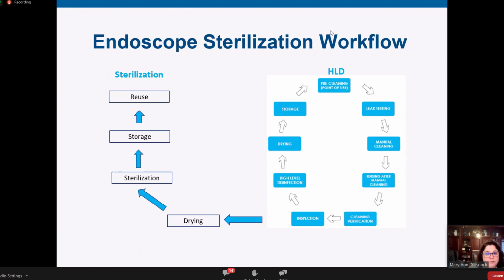And if you look in the endoscope manufacturer's IFUs, normally at the beginning of that reprocessing manual, it has a workflow. So it tells you what steps you still have to do to get to high-level disinfection, and then what steps you have to do for sterilization. So normally those IFUs don't say you disinfect and then sterilize. You do the beginning part of the process. So you do your point of use treatment, leak testing, manual cleaning, rinsing. Then you're going to do your cleaning verification test and your external inspection with lighted magnification. You may be using a borescope at this point. You may not be, but then you stop there.